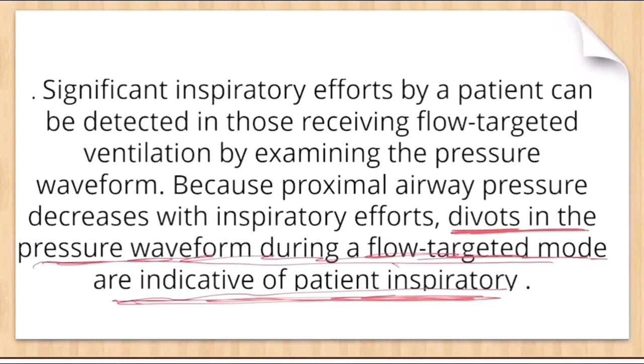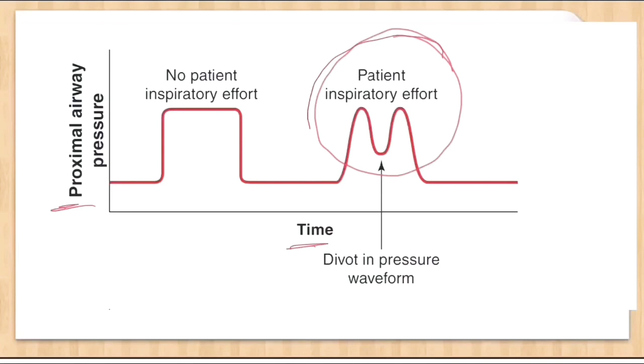Deflections in the pressure waveform during the flow targeted mode are indicative of patient inspiratory efforts. So you can see in this figure, pressure versus time, there is the flow targeted mode. Flow is targeted. Okay, you can see the dip in the inspiratory phase of the pressure. That will tell us that there are inspiratory efforts by the patient.